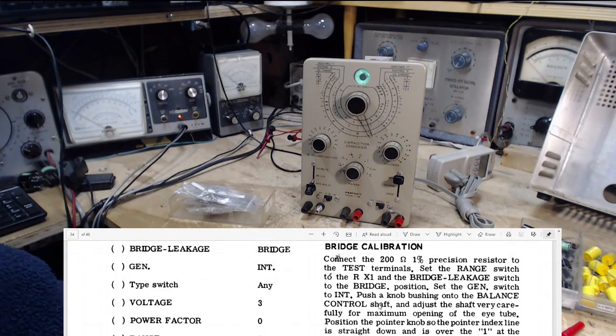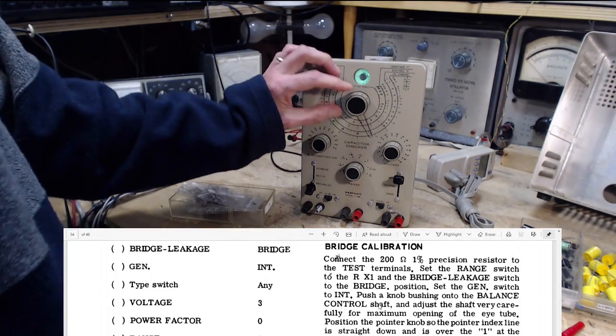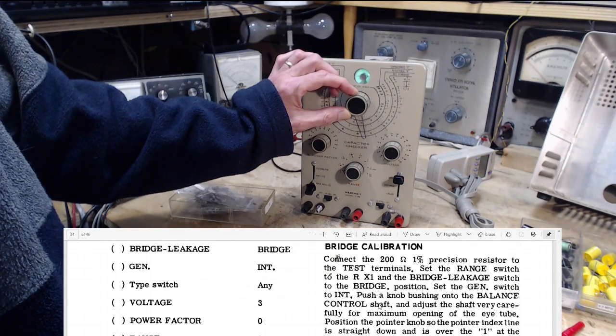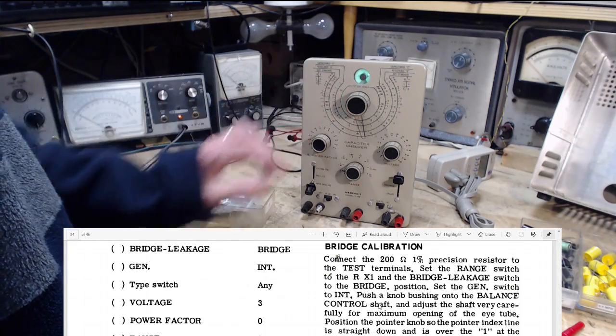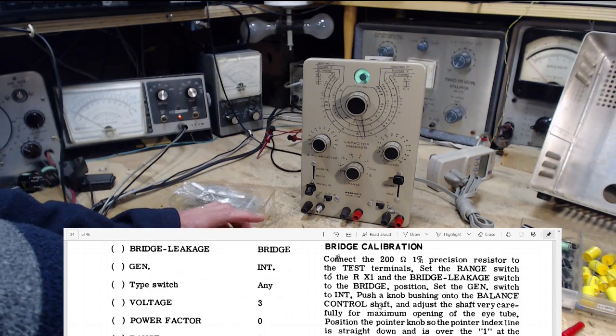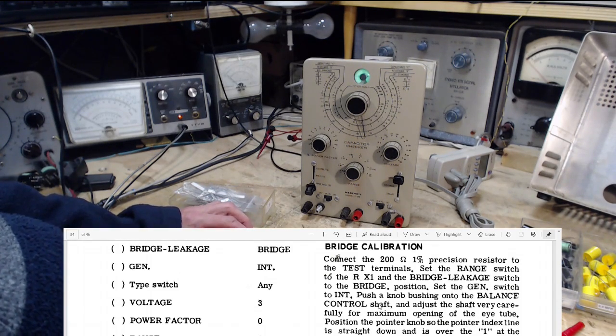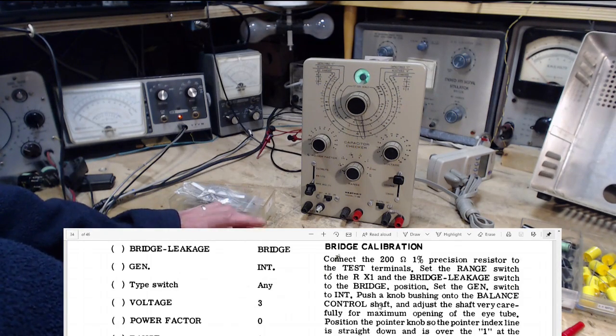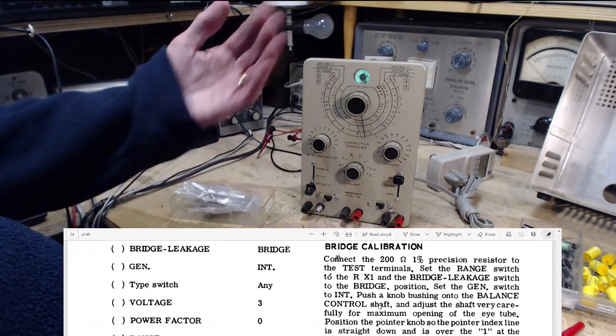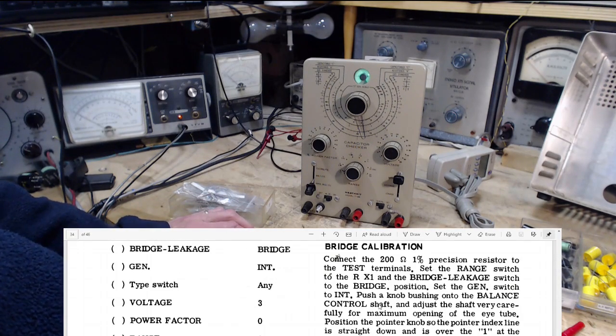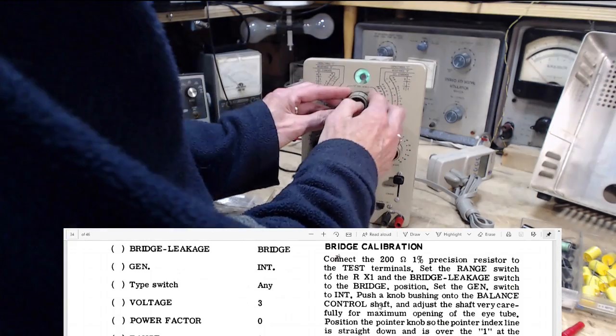And what's it say exactly? Adjust the shaft very carefully for maximum opening of the eye tube. Position the pointer knob so the pointer index line is straight down and is over one. It's not. It's off by a little bit. This is the primary calibration of this dial. Once this is done, the pointer, then from then on you do all the rest of the calibration with where the pointer is. It's not in the right spot. Oh my gosh! How can you deal with this?